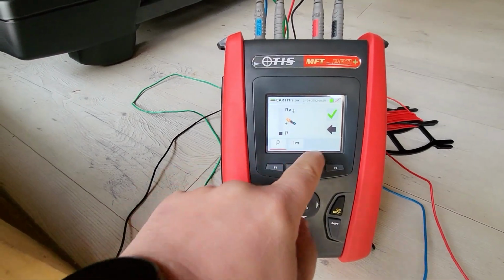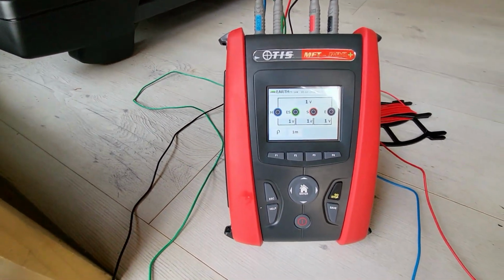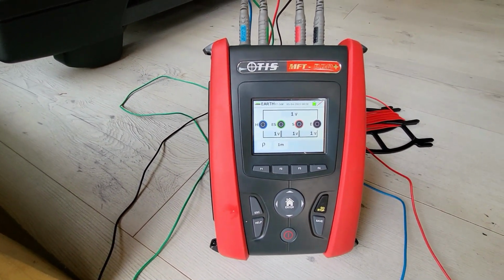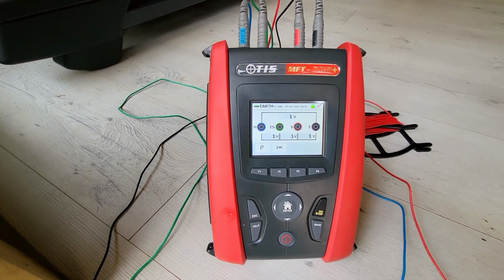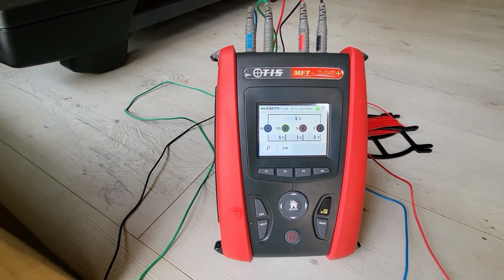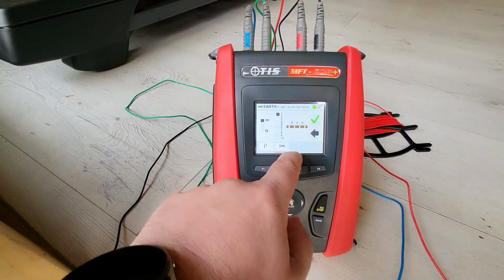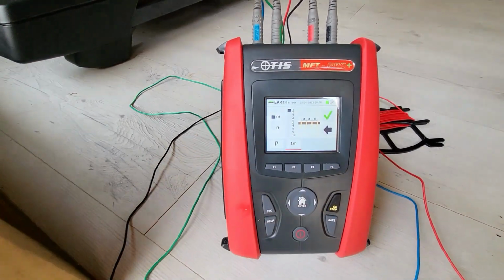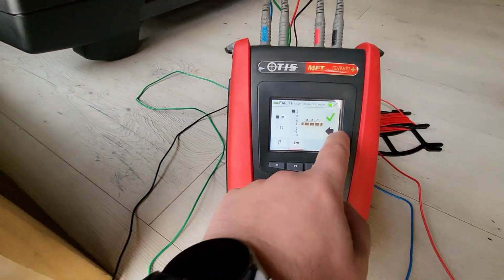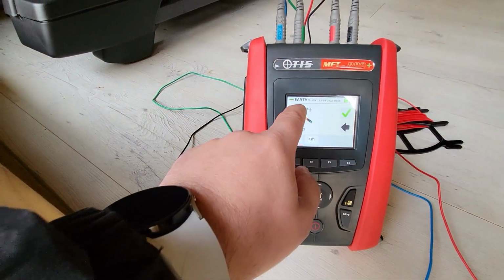Also you can do your 4-prong tests, so you don't need to use an electrode itself - you can just check the resistivity of the earth by putting your probes in the ground and carrying out some tests, and you can set the distances between those in this little scale here. So yeah, pretty useful instrument.